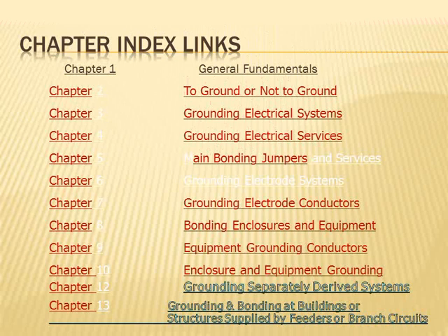So when we talk about grounding electrical systems, these are the systems we are going to go over. Then grounding the electrical service. When you get into the service, here's my 4,000 amp switchgear or my 100 amp panel in my house. How do you ground and bond right at the first panel? That chapter talks about grounding at the service: the main bonding jumper, the grounding electrode conductor, the grounding electrode system, and bonding of enclosures. I'm going to summarize these in a couple of sheets.